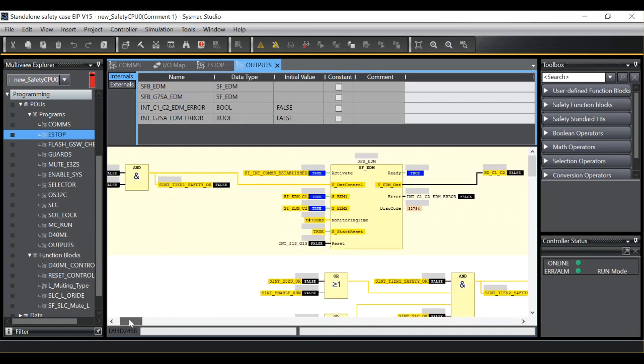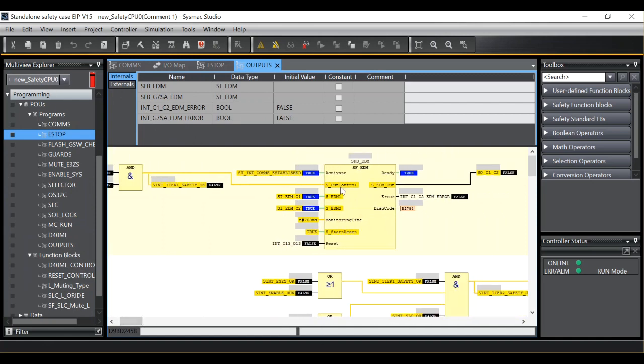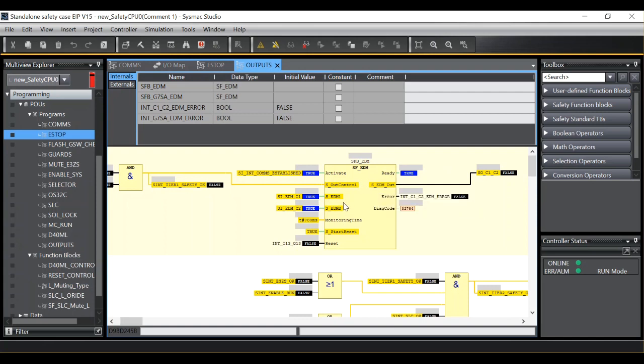The result of this is that none of the essential safety function block code will start to run until all the IO is reported back in that it's connected to the network and it's up and running.